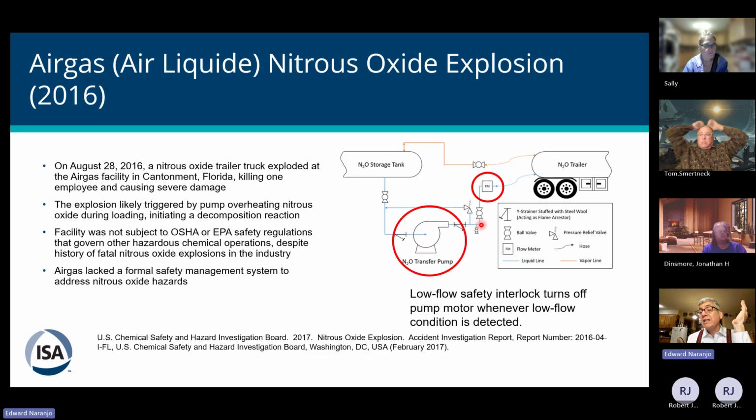Well, if you know that this sensor is that critical, how often do you need to maintain it? How do you know when it is not working? And what happens when it fails? Then what do you need to do? If you had designed this properly through a PHA, you would have had some bypasses. You would not have depended on one single sensor, ever.